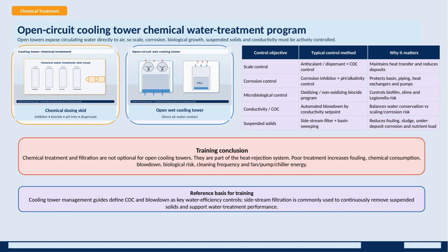Another essential control is managing the conductivity or cycles of concentration through automated blowdown, which balances water conservation with the risk of scaling and corrosion. Suspended solids are addressed with side stream filtration and basin sweeping to reduce fouling, sludge buildup, and associated corrosion risks.